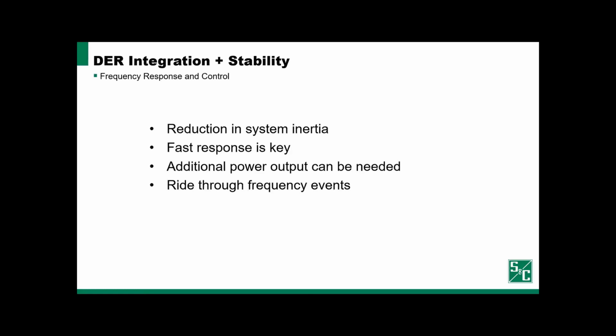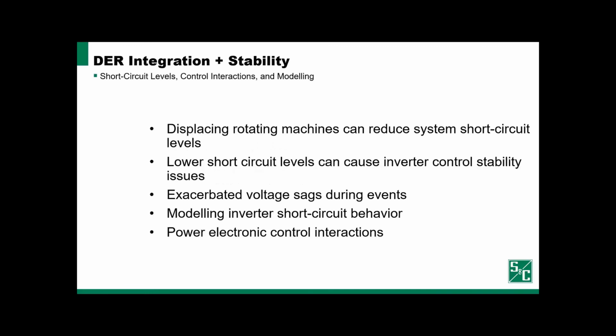Similar to the low voltage situations, it's imperative that our inverter-based resources and our distributed resources ride through frequency events as they become a more significant component, to ensure that they can maintain system power needs. The last three stability concerns I think really go together, and I want to interlink. Those three concerns are system short circuit levels, control interactions between devices, and how we're modeling the power system.